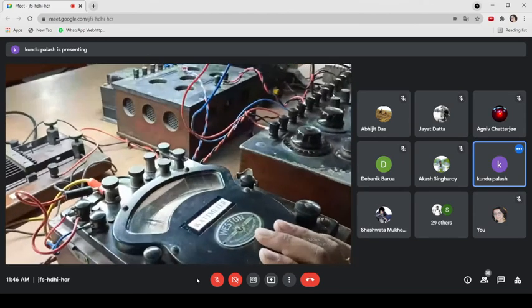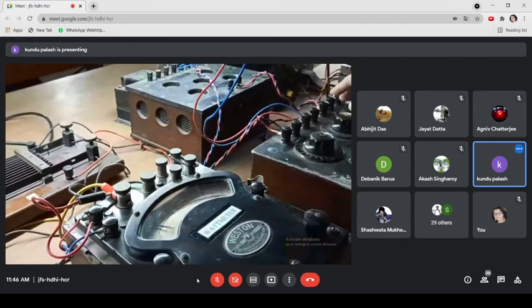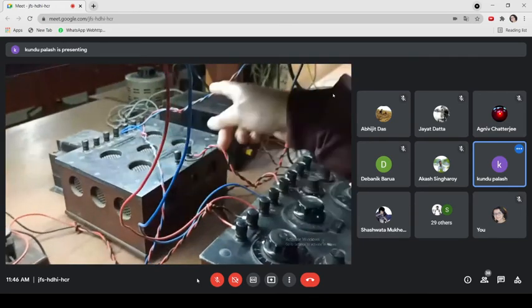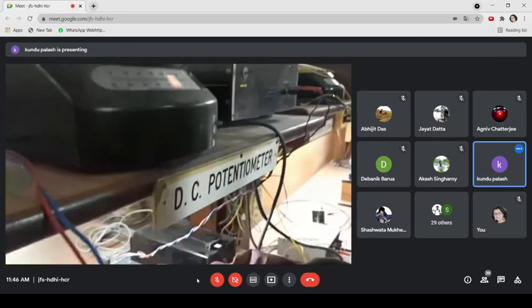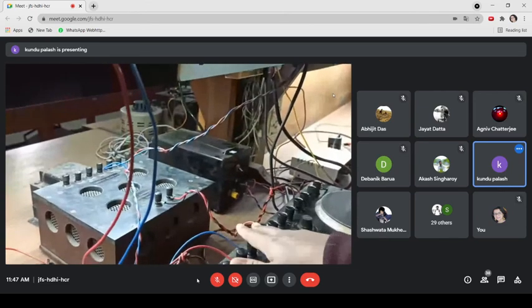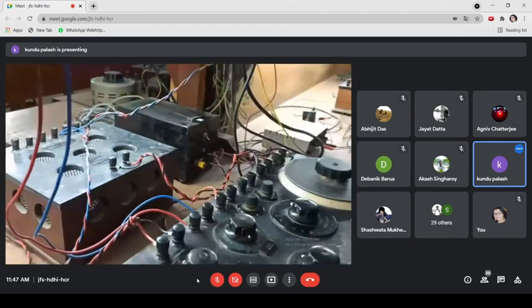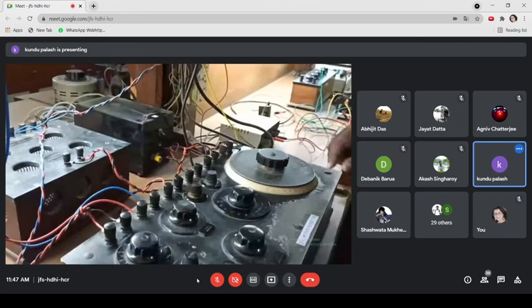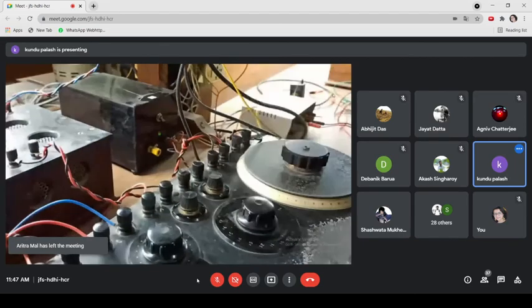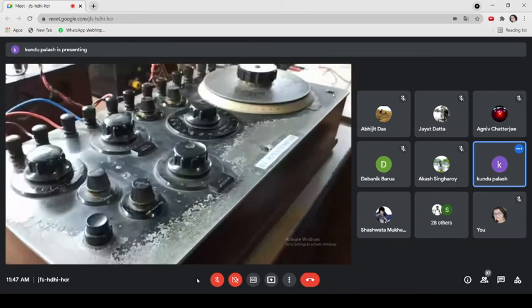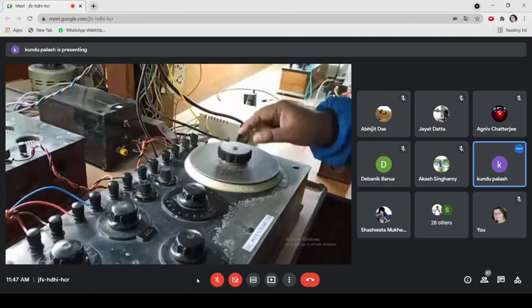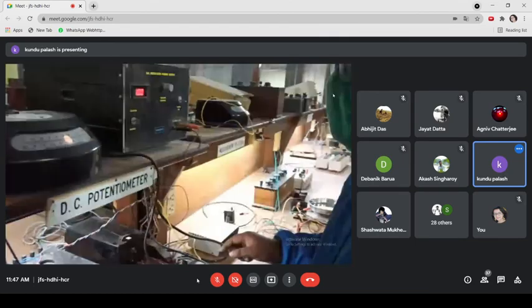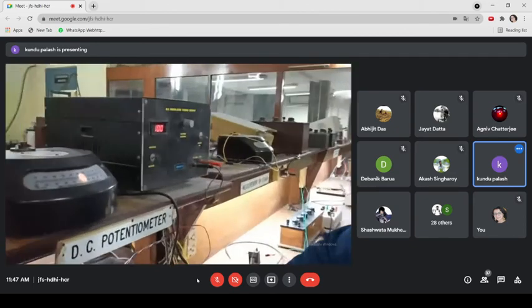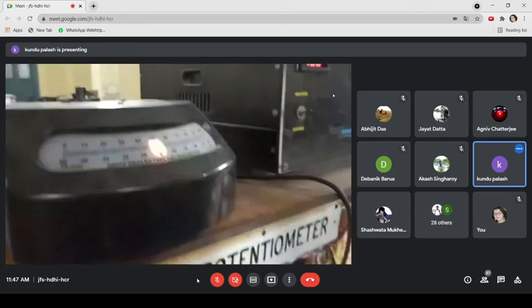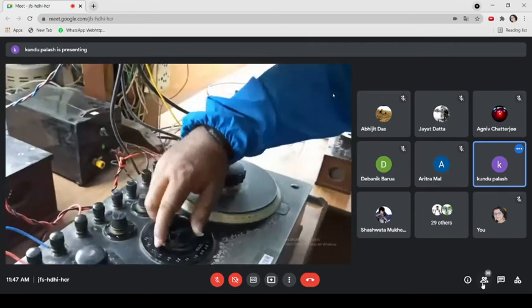So first, we will calibrate the potential coil. As you know, the potential coil is charged with this 100 volt, and through this volt ratio box, we are getting approximately 1 volt at this terminal. So change the selector switch to terminal 1, and you can see this potentiometer is in test mode. Now when we click the push button, you see there is a deflection in the galvanometer.